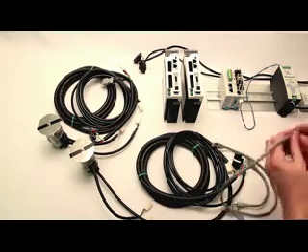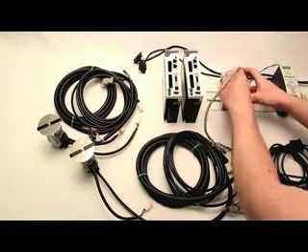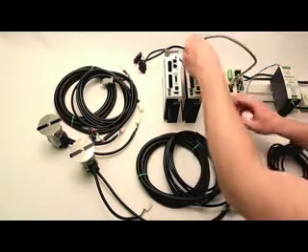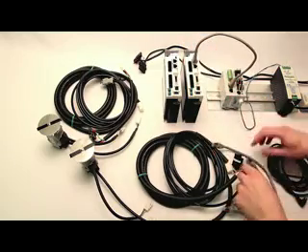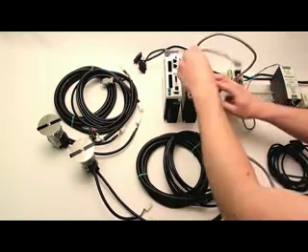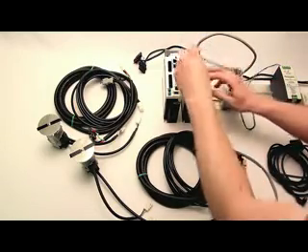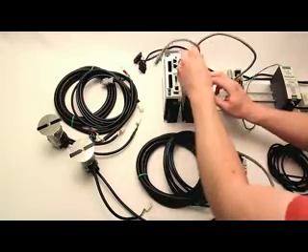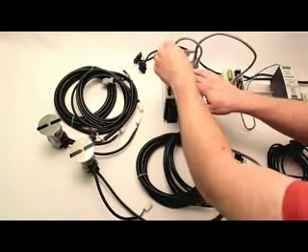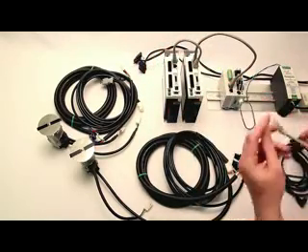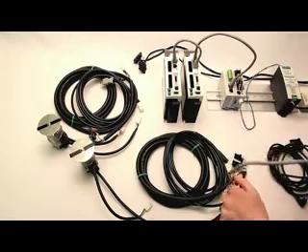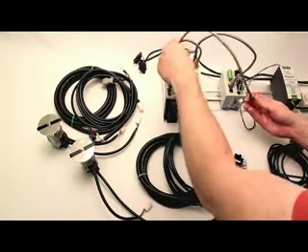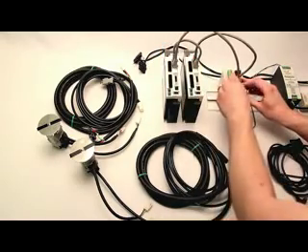Now it's a very simple ring topology. I'll use the transmit of the PLC and put that to the receive of the first drive, then the transmit of the first drive to the receive of the second drive, and lastly I will take the transmit of the second drive and put it to the receive of the PLC.